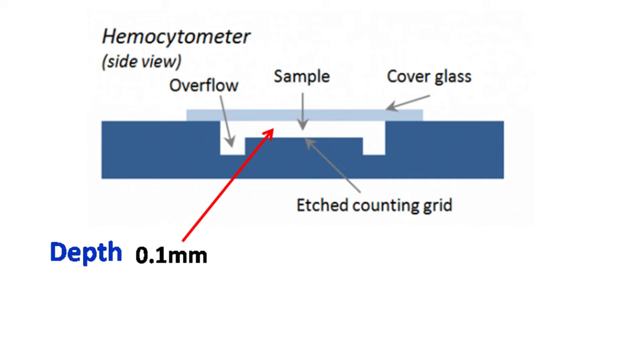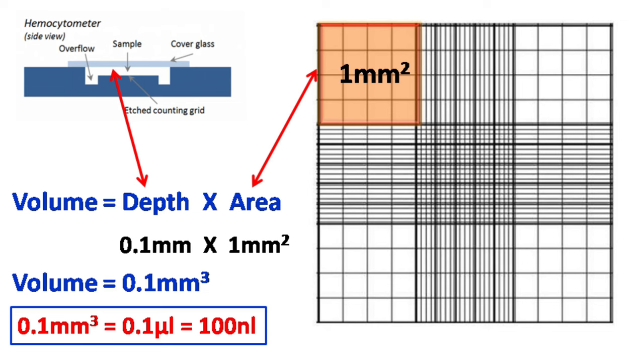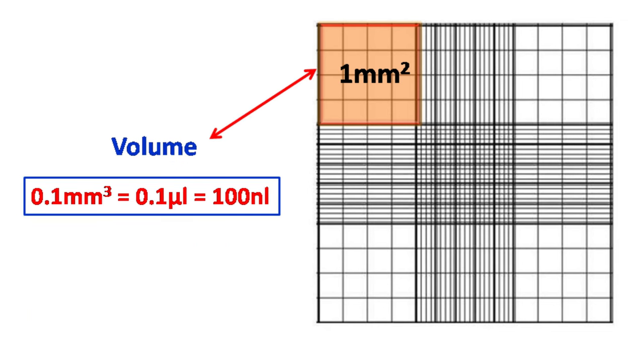And the depth of the chamber is around 0.1 millimeter. Now if we multiply area by depth, then what we get is the volume. And here we come to the magical number of 100. The volume occupied by each of the large squares is around 100 nanoliters. And that's the only thing you need to remember: 100 nanoliters.